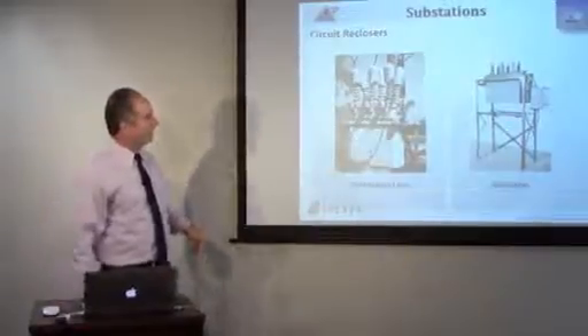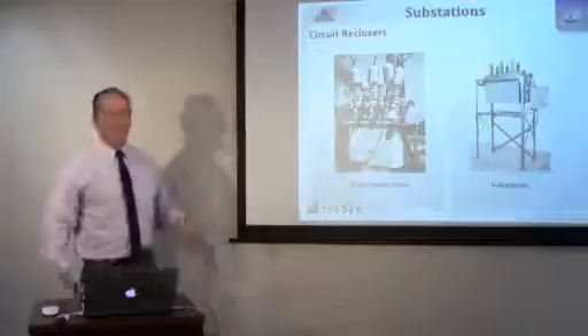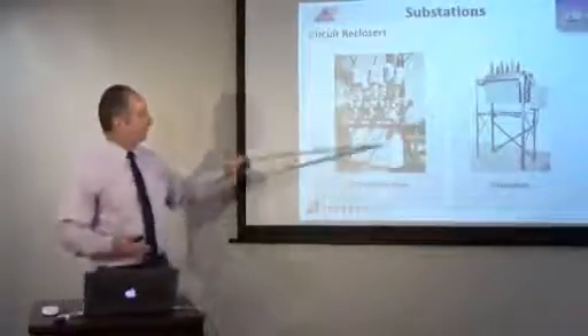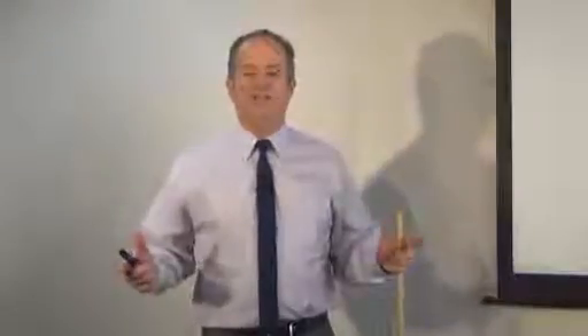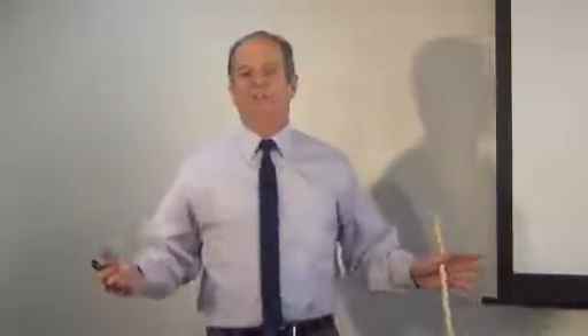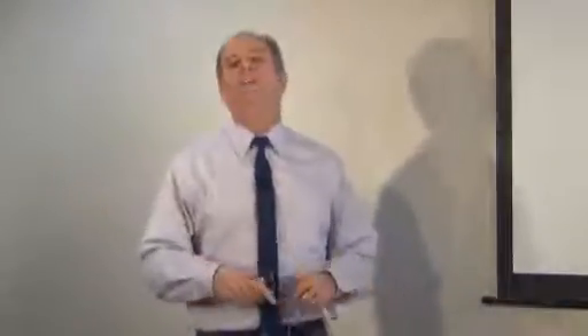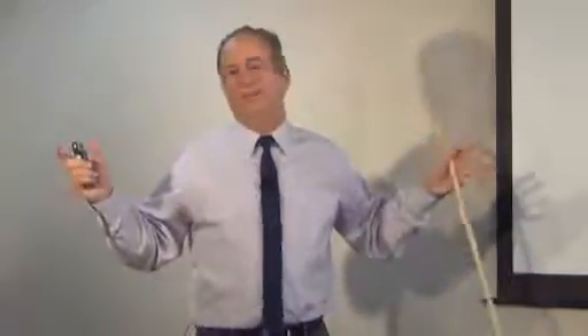But the idea here is when there's a fault on a distribution line, the recloser senses it through the CTs that are internal. And if there's an increase in current beyond its set point, it'll trip an open circuit breaker. But it'll wait 5 seconds and automatically reclose and re-energize the circuit, which is great. When you have a lightning strike and it hits and all the lights go out, 5 seconds later all the lights come back on without blowing a fuse or sending a troubleman out to fix the problem.